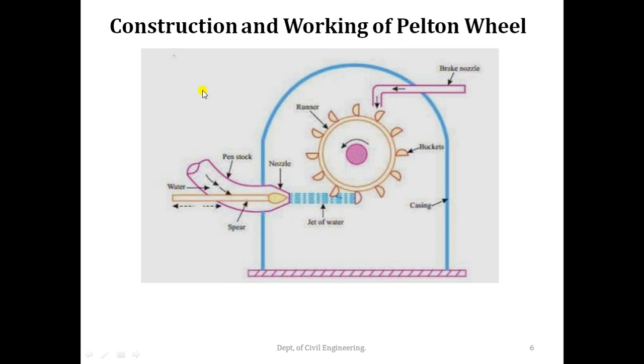A Pelton turbine consists of a rotor at the periphery of which are mounted equally spaced double hemispherical or double ellipsoidal buckets. Water is transferred from the high-head source through a penstock — pipes of larger diameter carrying water under pressure — fitted with a nozzle. As water passes through the nozzle, it gets converted into a high-speed jet. A needle spear moving inside the nozzle controls the water flow through the nozzle, providing smooth flow with negligible energy loss. By moving the needle spear in and out, we can control the rate of flow.